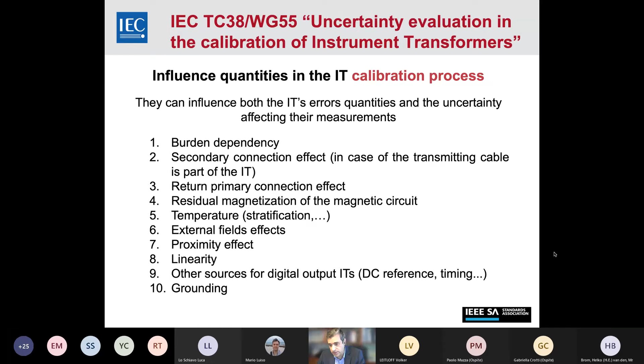Then we considered the environmental quantities surrounding the system that can be considered. We have also considered all the sources of uncertainty in the calibration system, in particular the metrological characteristics of the reference device, the bridge or comparator, depending on how we call it, used for evaluating the uncertainty, the ratio error, and the phase error or phase displacement.